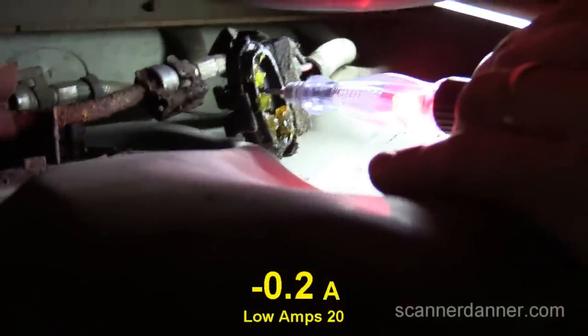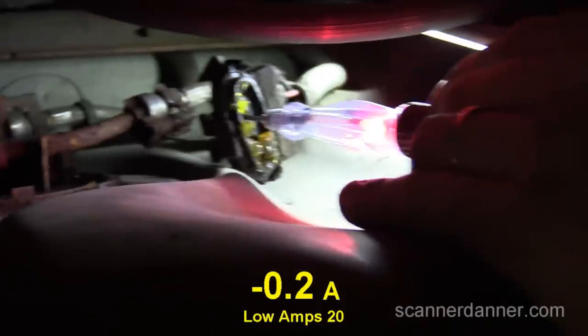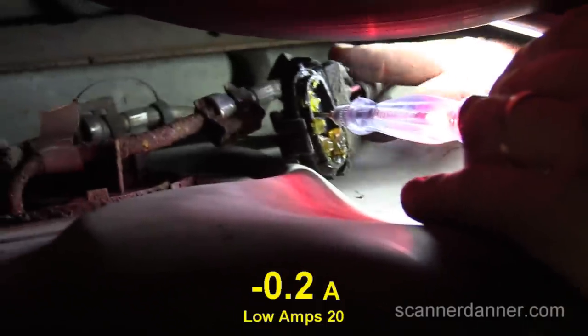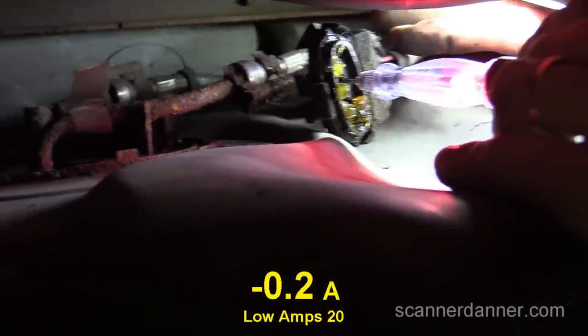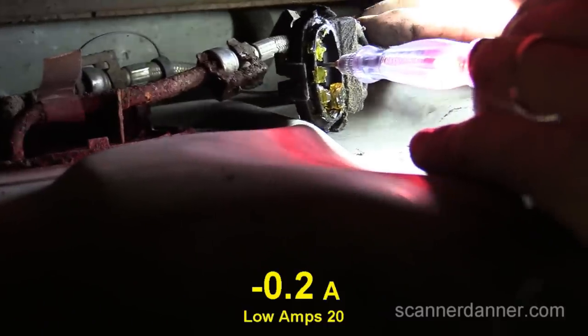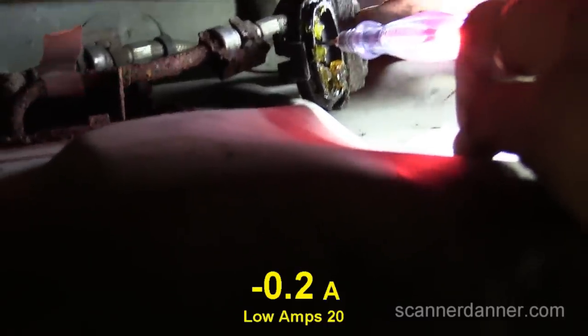So how's my power feed to my pump? Good, it is good, my wiring's fine all the way back here. The only other thing I need to check is this pump ground, which is next to it. And I need a power feed to do that because I'm load circuit testing it, that's how I'd like to do it.